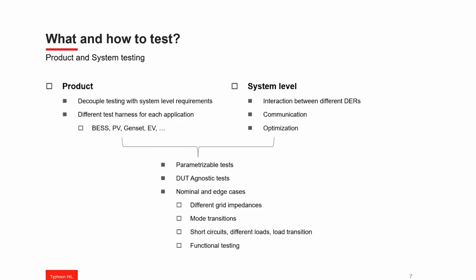On optimization, you could run any number of scenarios in order to, for example, reduce the diesel consumption of a genset while islanded, properly do peak shaving, frequency support, or increase the profits on a dynamic market. This is also where you could be testing different AIs for all these cases and compare the results.